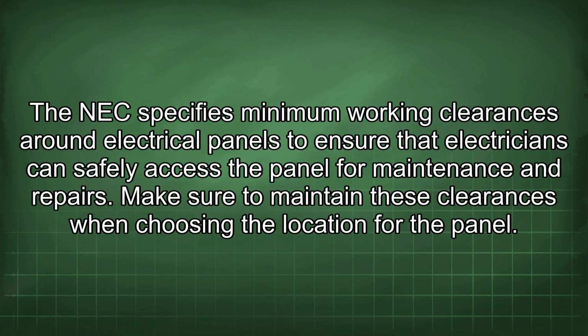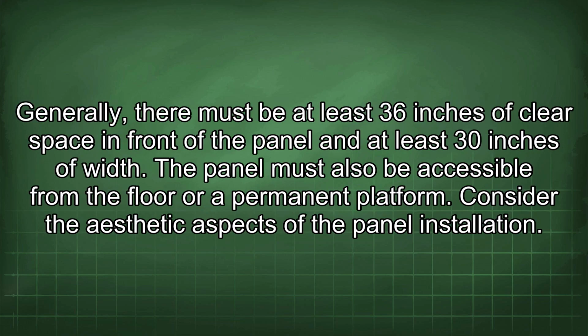The NEC specifies minimum working clearances around electrical panels to ensure that electricians can safely access the panel for maintenance and repairs. Make sure to maintain these clearances when choosing the location for the panel. Generally, there must be at least 36 inches of clear space in front of the panel and at least 30 inches of width. The panel must also be accessible from the floor or a permanent platform.